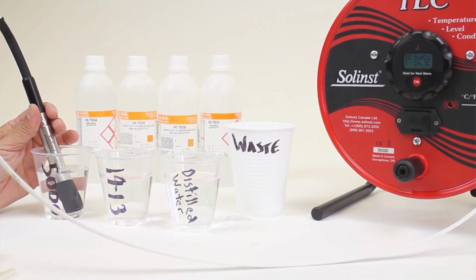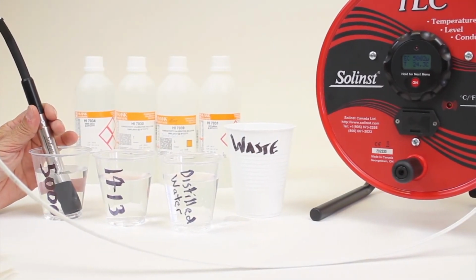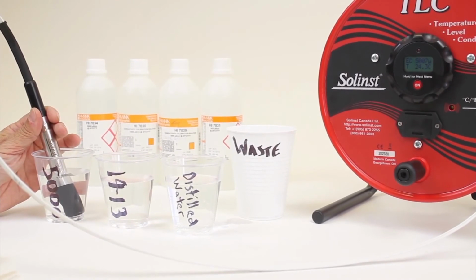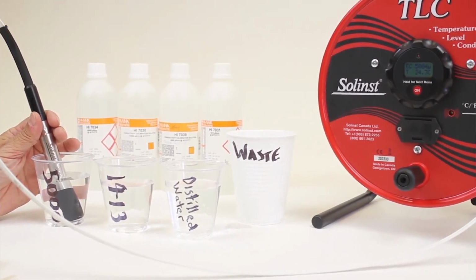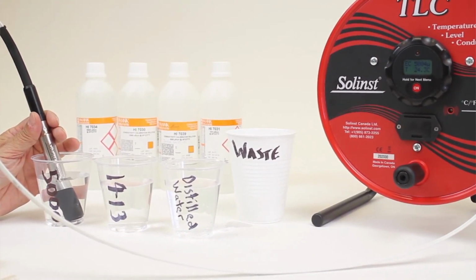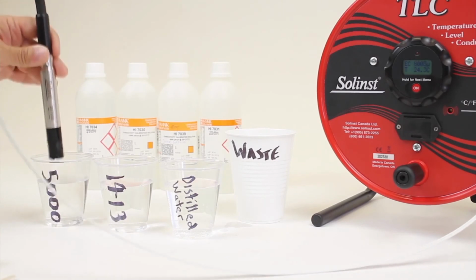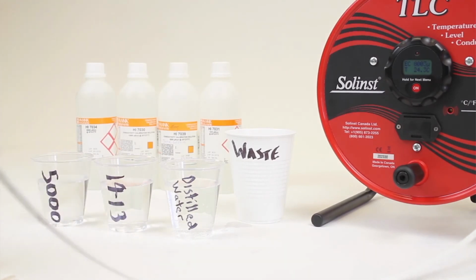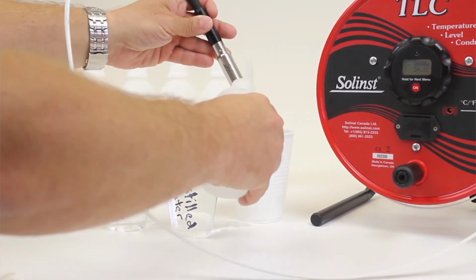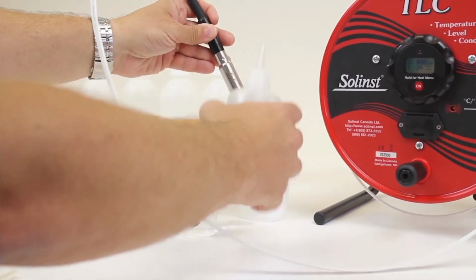It shows a reading in this calibration solution of 5002, and you'll note that the temperature is still 24.3. It's moved between 24.3 and 24.4, so it's very consistent. That's giving me a good reading. Now my conductivity calibration is complete. I'll dry that off, I'll clean it off, I'll complete the operation.